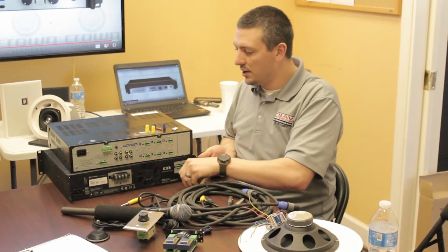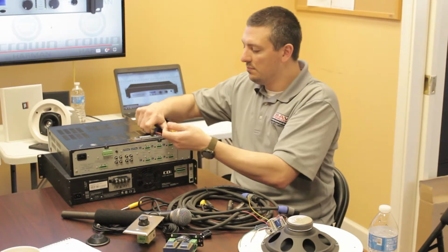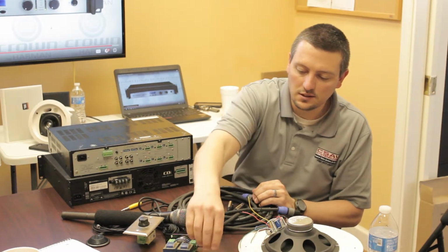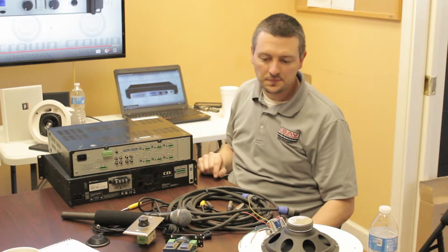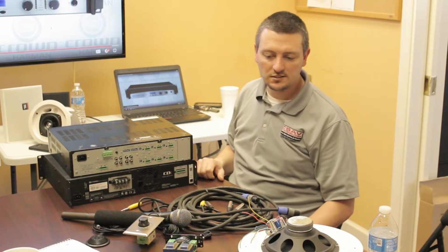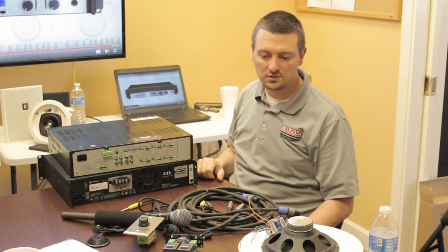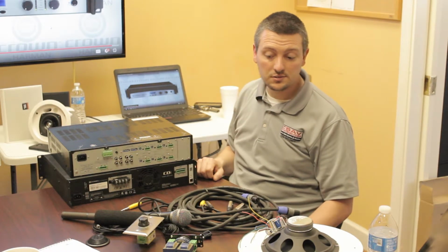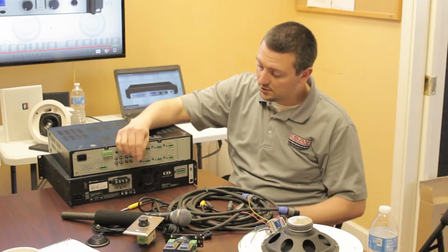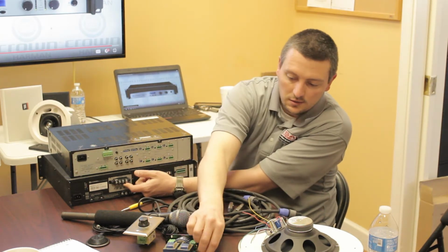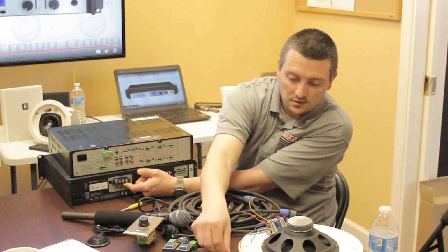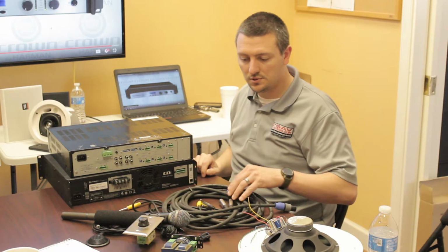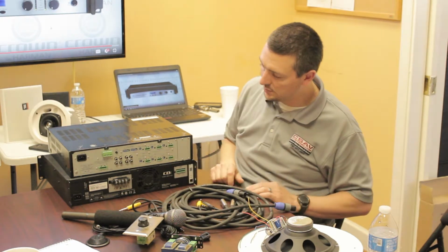But I can't stress enough connectors and terminations. That's so crucial to everything we do. Many times I've been on service calls to fix things just because stuff wasn't terminated properly or the connections weren't tight enough. So if you're using an amp, like I said, don't stick the wire in there and screw it down. Make sure you stock your tool bag with different sizes of fork connectors or spade connectors and wire nuts, because we use them on every single install, every job you're on.